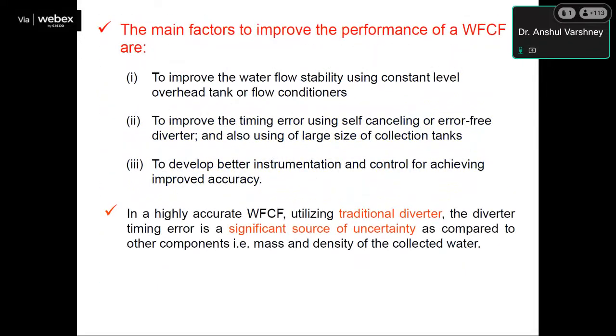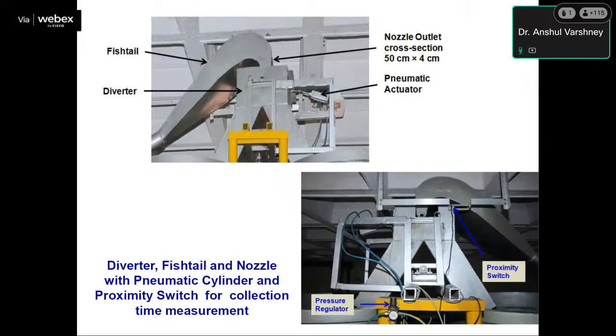The main factors to improve the performance of a water flow calibration system are to improve the water flow stability using a constant level overhead tank and flow conditioners, to improve the timing errors using self-cancellation or an error-free diverter, and also using a large collection tank and developing better instrumentation and control for achieving improved accuracy. In a highly accurate water flow calibration facility utilizing a traditional diverter, the diverter timing error is a significant source of uncertainty as compared to other components like mass and density of the collected water.